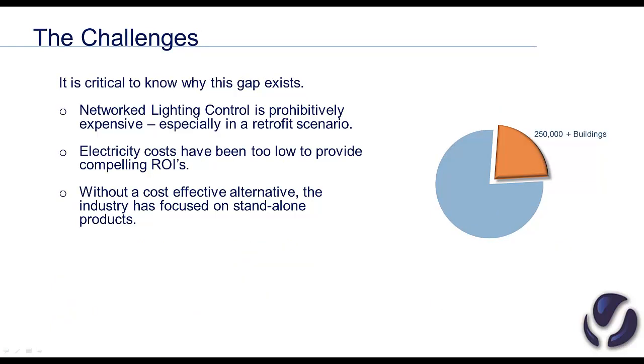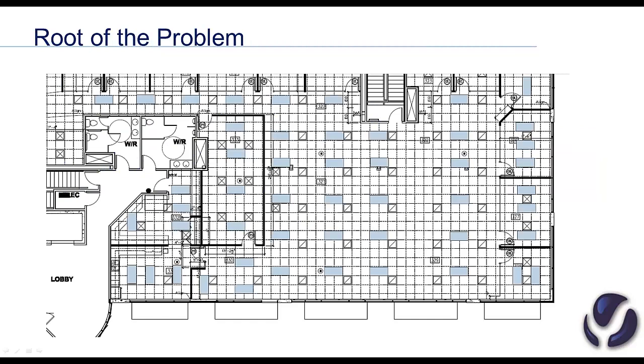It's very important to understand why this gap exists. The reasons are simple. Lighting control is prohibitively expensive to install in an existing building, and if electricity costs are relatively low at that time, the return on investment is even less compelling. As a result, you see a world where virtually everything is connected, but yet the lighting control industry is dominated by standalone product. To understand why it's so expensive to install lighting control in an existing building, we need to understand how lighting circuits are wired.